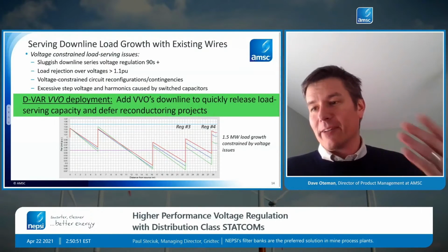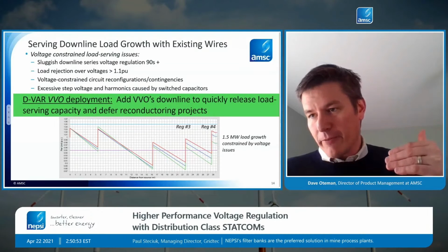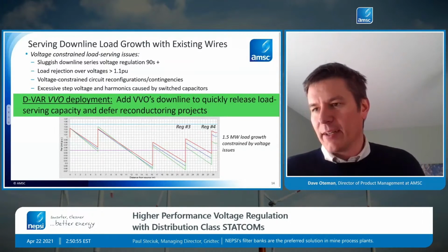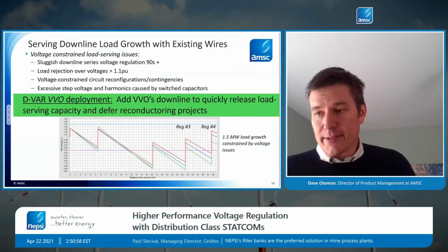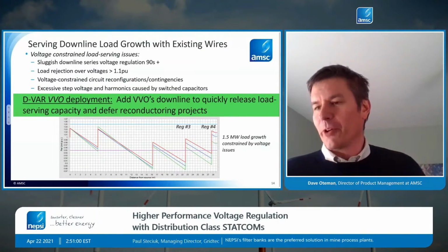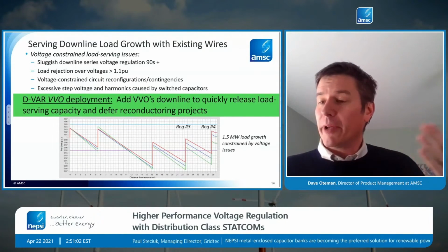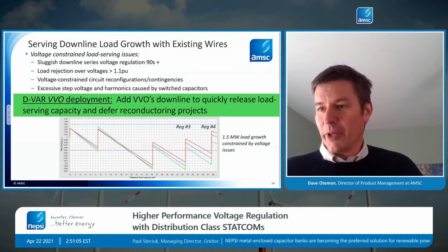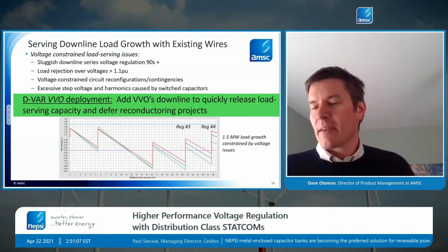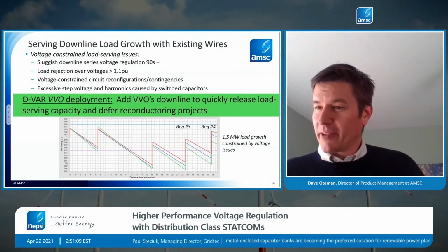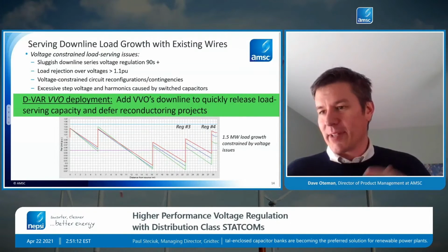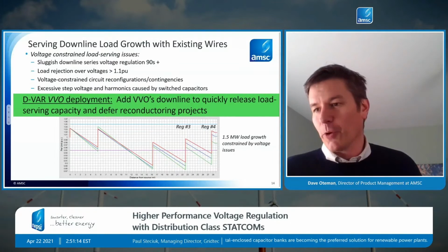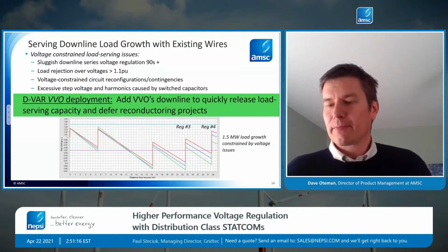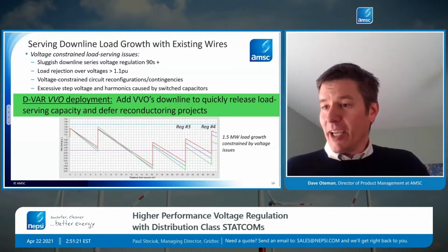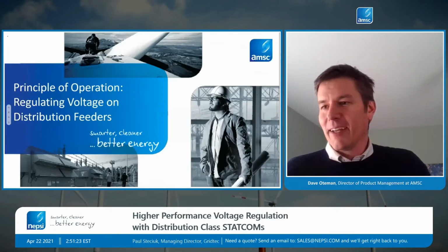So at some point, obviously, if a load of like 5 megawatts, for example, is needed, it's not a voltage issue anymore, it's a thermal issue. And at that point it would be appropriate to, for example, reconductor or run a new feeder. But when it's only being constrained due to voltage, that's where the STATCOM is also a really nice tool for being able to serve this load. So that brings us through the main applications that I wanted to share today.